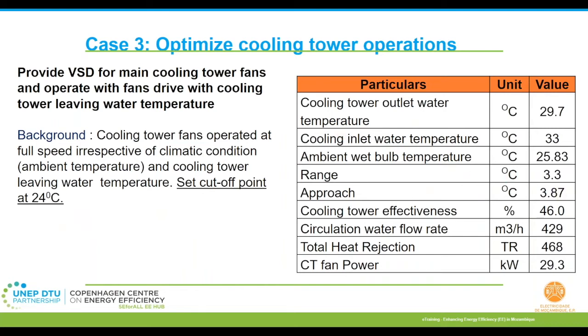Optimizing of cooling tower operations. So basically, there was a building complex which had water-cooled chillers for their air conditioning needs, and they have cooling towers to reject the heat from the chillers. So we have seen the role of cooling towers in the HVAC systems. The cooling tower fans were operating at full speed, irrespective of the ambient conditions.